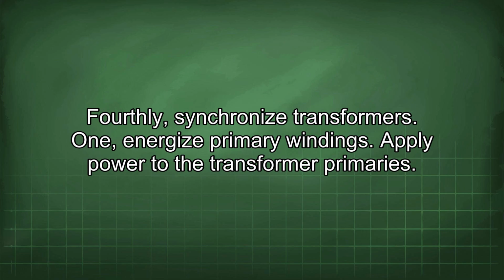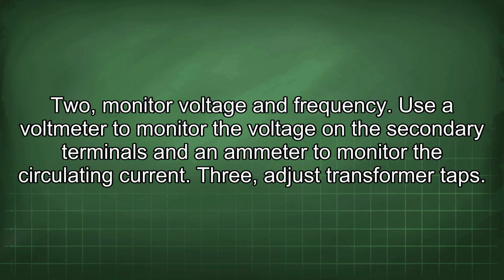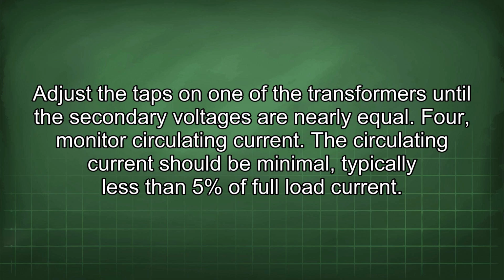Fourthly, synchronize transformers. 1. Energize primary windings. Apply power to the transformer primary. 2. Monitor voltage and frequency. Use a voltmeter to monitor the voltage on the secondary terminals and an ammeter to monitor the circulating current. 3. Adjust transformer taps. Adjust the taps on one of the transformers until the secondary voltages are nearly equal. 4. Monitor circulating current. The circulating current should be minimal, typically less than 5% of full load current.